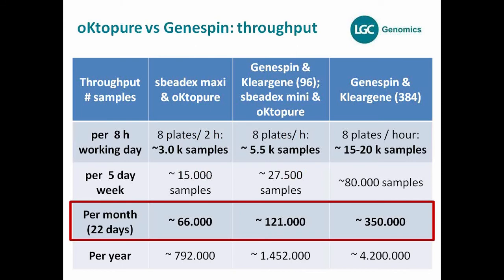The most important decision factor between platforms is throughput. The sbeadex maxi on oKtopure processes about 3,000 samples per day, while the Kleargene GeneSpin in the 384 format can handle about 20,000 to 50,000 samples. The decision depends not only on throughput, but also on DNA yields needed, processing speed, and how many people you have in the lab. Additionally, you can use MultiDrop instruments with the GeneSpin Kleargene to further increase throughput if needed.